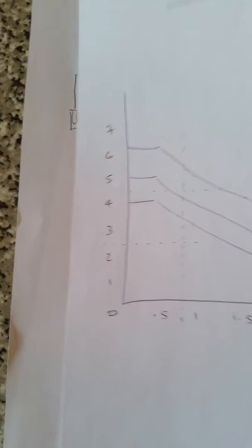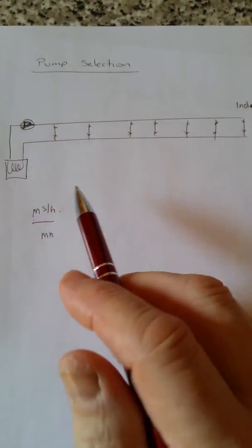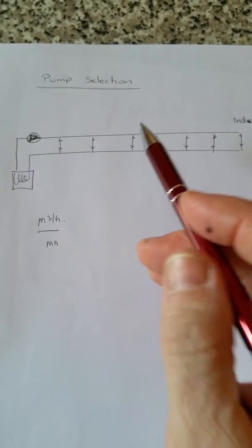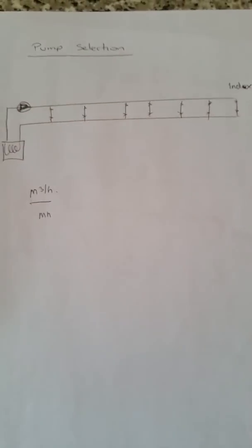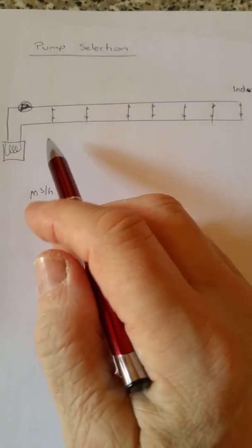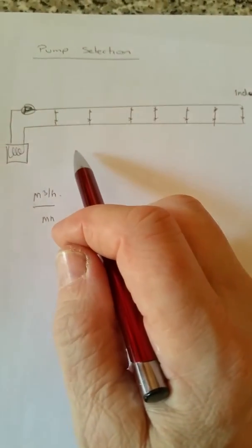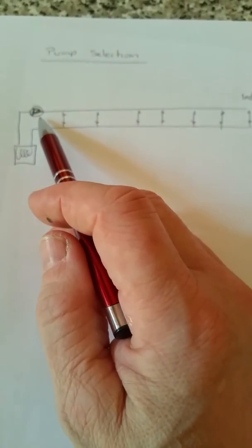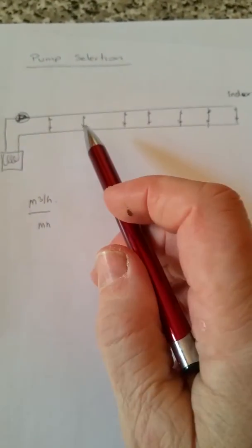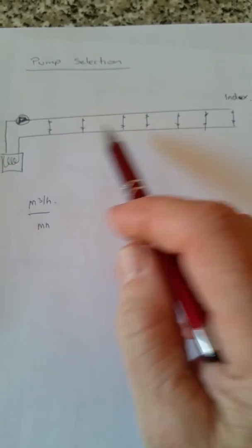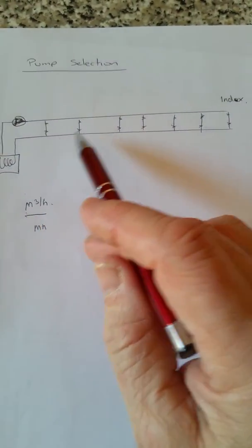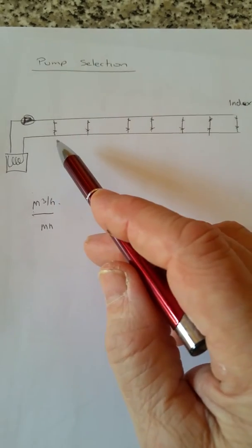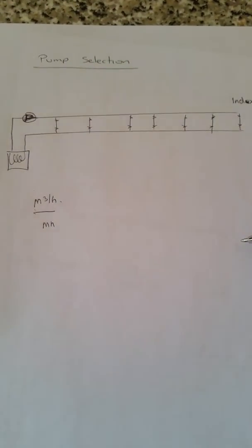I'd just like to cover a little something back on here. People have been talking about balancing systems, and I'm a little bit concerned about the method, where they're using DT and mean temperatures, and this really isn't quite the full story. If I give you an example, if the pump isn't suitable for the system, and it often isn't, you can actually get the radiators balanced, and you can get equal DTs across the radiators by adjusting them, but you will not have the right flow rate and the right heat output through the radiators.